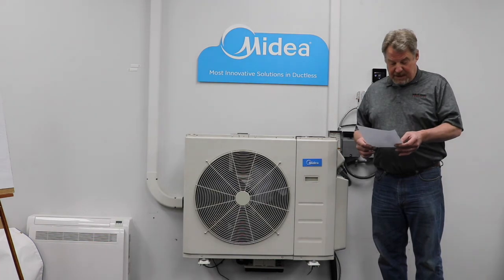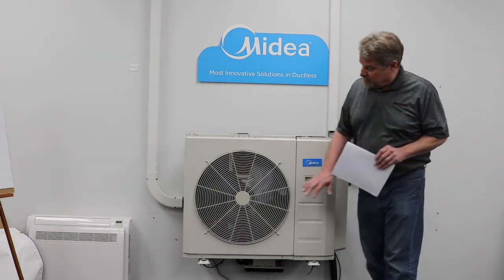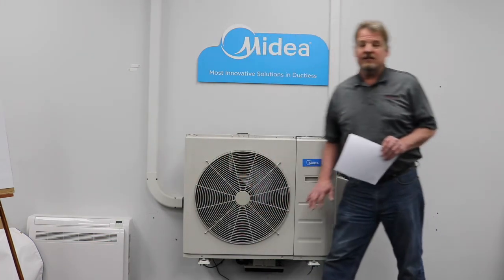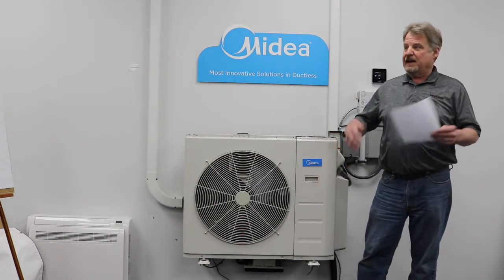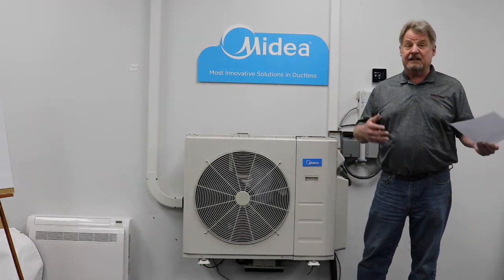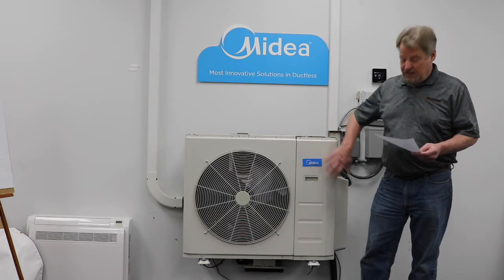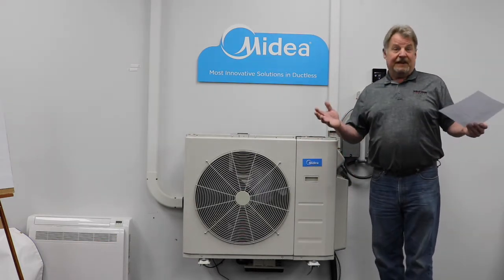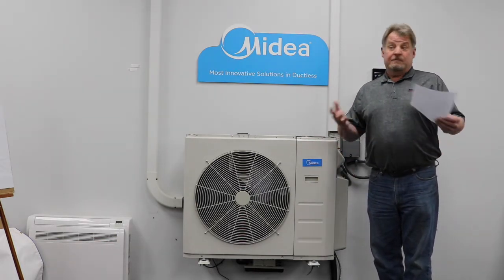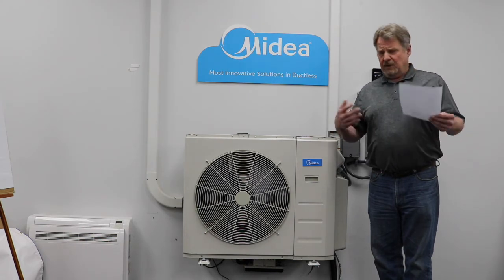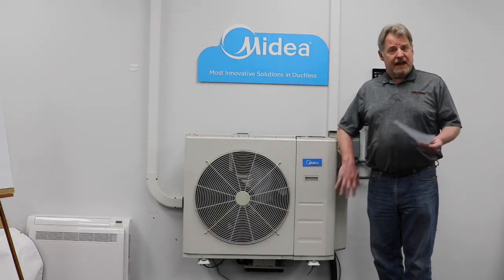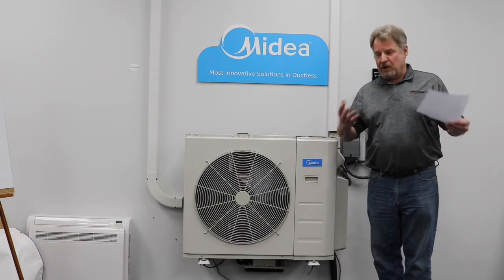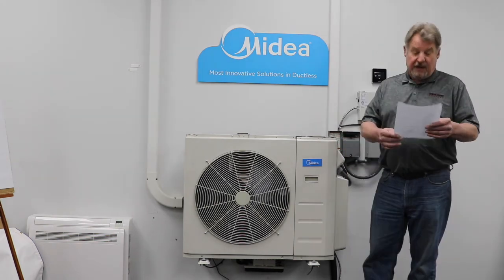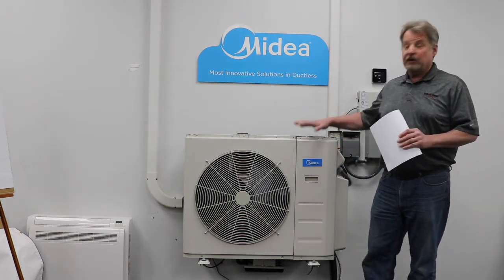Further on down the line, 37 to 41 is going to tell me what position each of the expansion valves is in. So if I've got a zone that's calling, but I'm not getting cooling, I can go in here and say, okay, port A, the valve is open 80 pulses. So 80 pulses is pretty far open. If I'm not getting cooling, then I may have a problem with my valve, or I might have a problem with charge, and so on. History of fault codes: I can look at what my previous fault codes were.